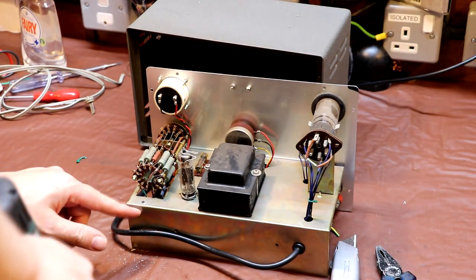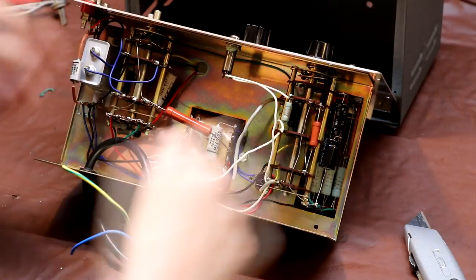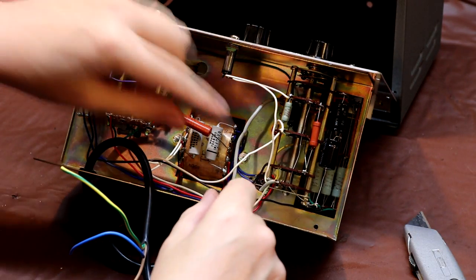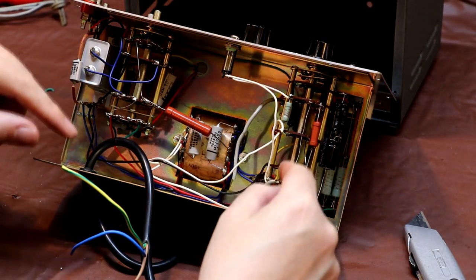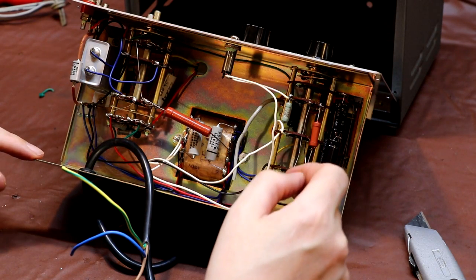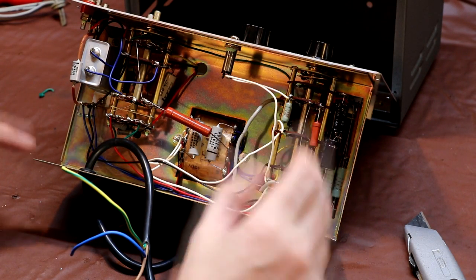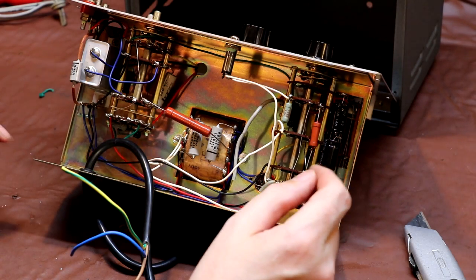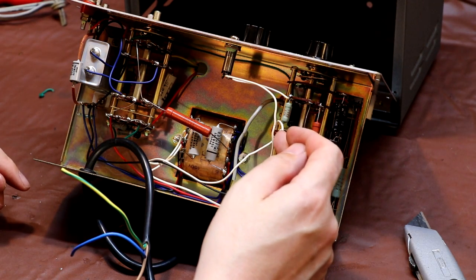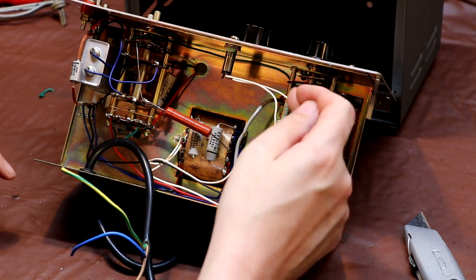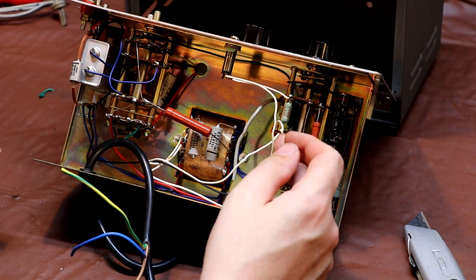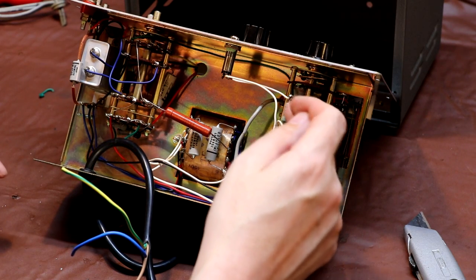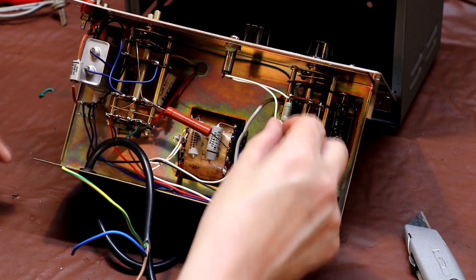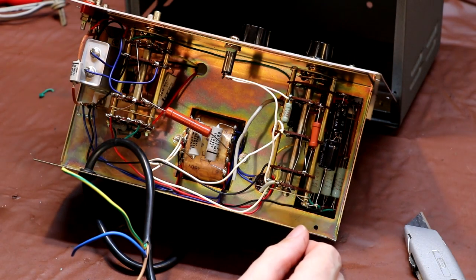So we're going to fix our earth terminal onto here. Now perhaps some of the mains wiring looks a little bit confusing, because you appear to see the mains wiring going to multiple places on this selector switch. But actually it's not as complicated as it looks, because a lot of these terminals on the side of the selector switch are not actually connected to anything on the switch itself. They are just terminals being used for the purpose of anchoring some of this mains wiring.